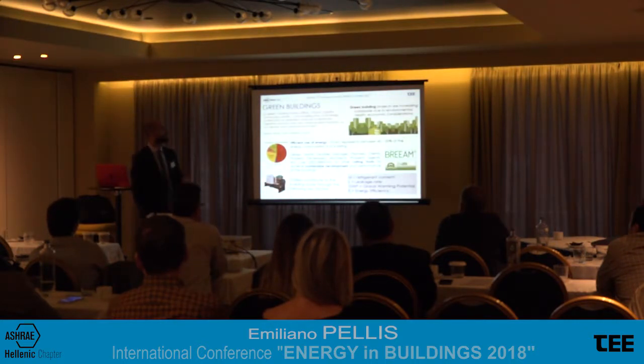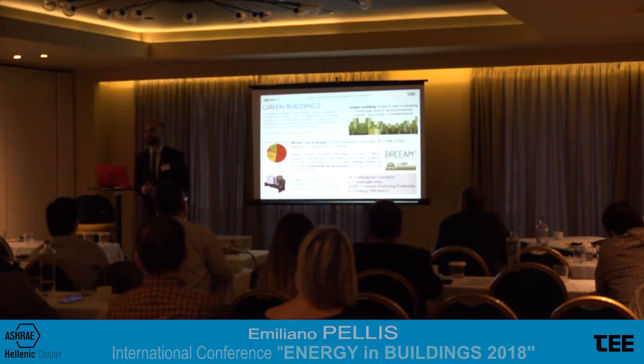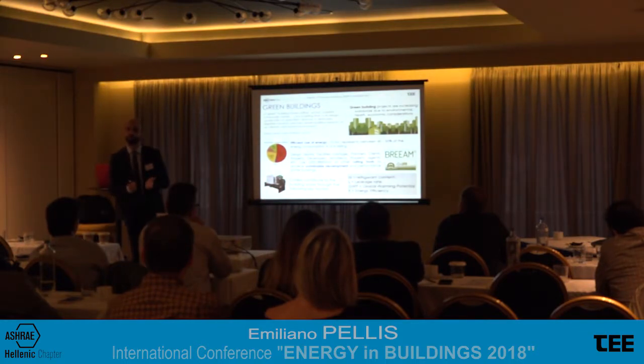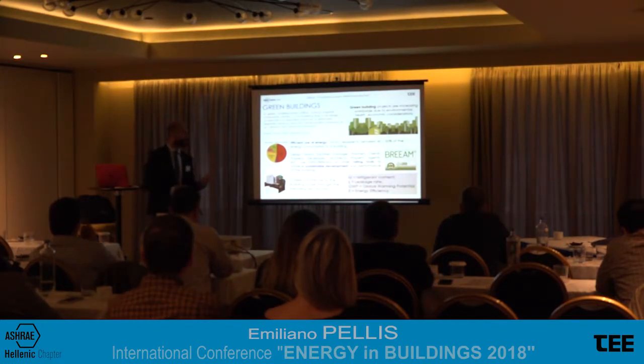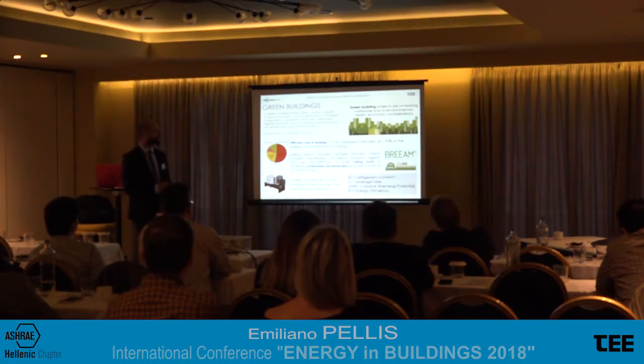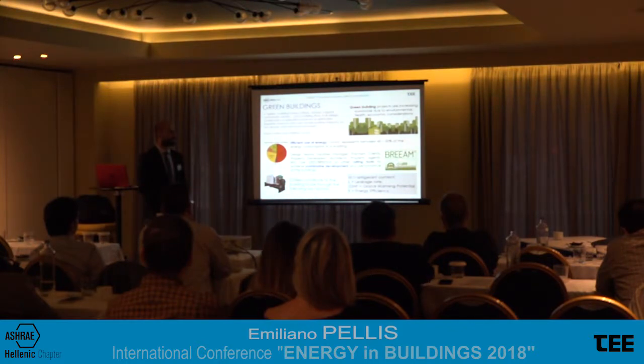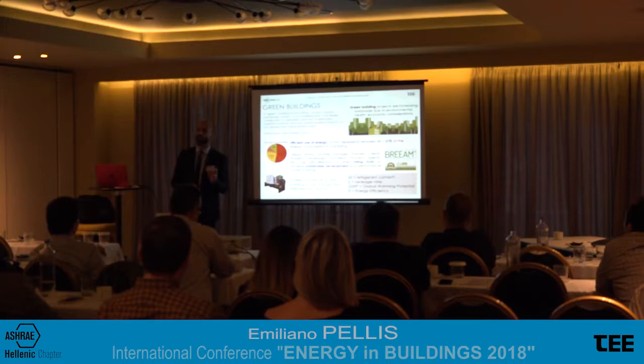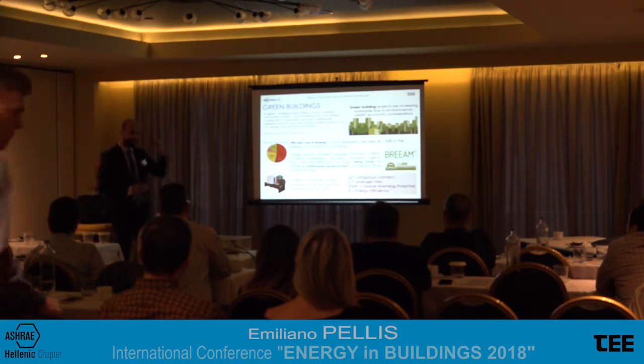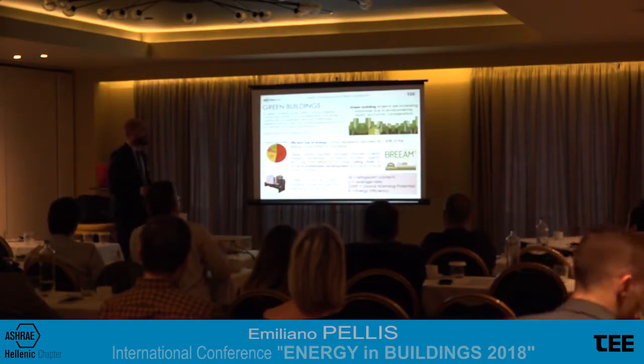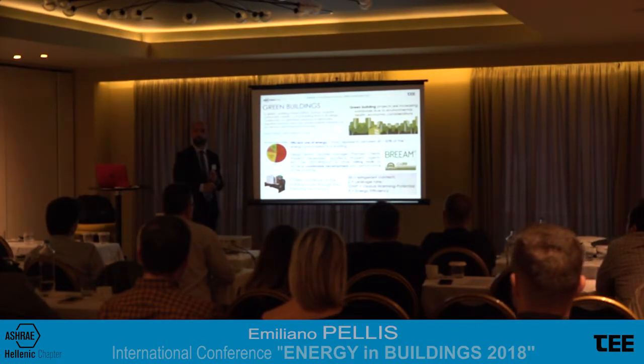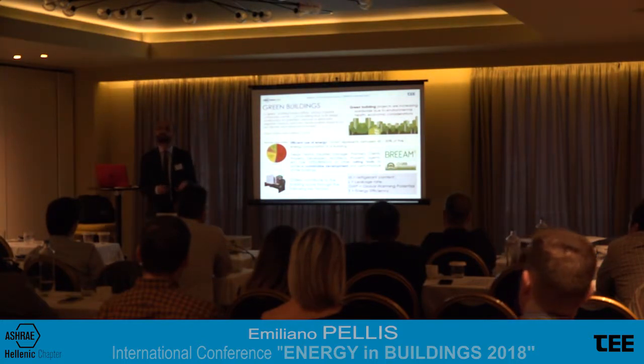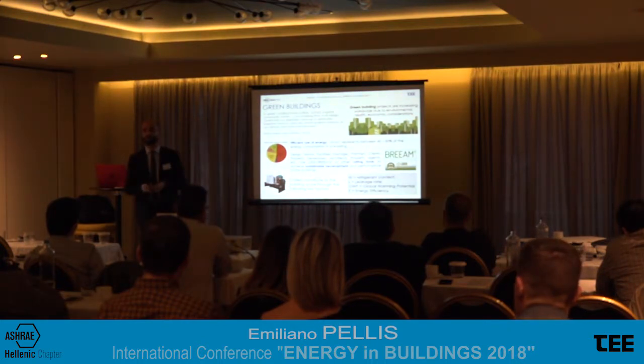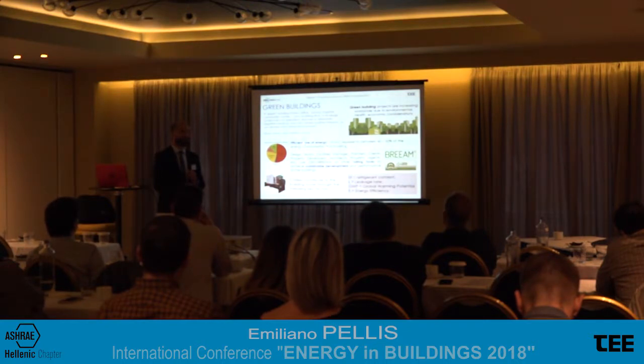So this is eco-design. The third point is green buildings. You know, a building is green when its design, its construction and operation have been optimized in terms of impact on the environment. A building can be certified as green according to one of the existing rating tools. The most popular are BREEAM from the UK and LEED, but there are also other rating tools, and basically the building needs to reach a score in order to be certified as a green building. There are many points that contribute to the achievement of this score. As you can imagine, one of the key points is the efficient use of energy within the building. And the HVAC represents, at least in the worst case, 35% or even 40% of the total energy consumption within a building. So you understand how important the contribution of the HVAC system is to becoming green.